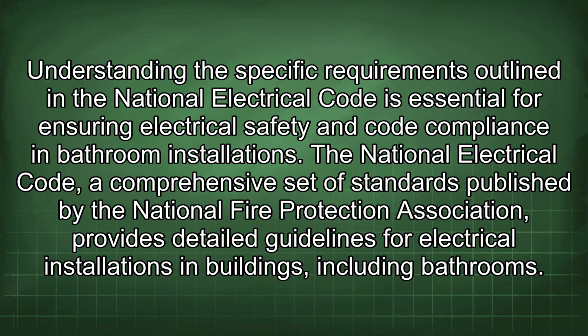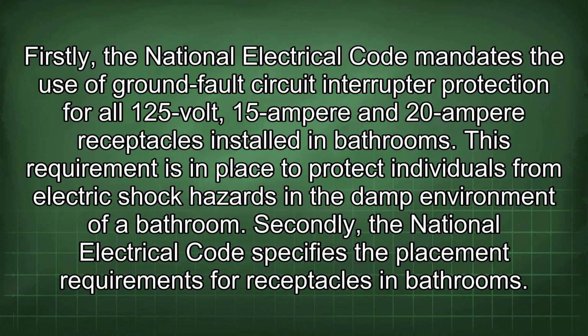Understanding the specific requirements outlined in the National Electrical Code is essential for ensuring electrical safety and code compliance in bathroom installations. The National Electrical Code, a comprehensive set of standards published by the National Fire Protection Association, provides detailed guidelines for electrical installations in buildings, including bathrooms. Firstly, the National Electrical Code mandates the use of ground fault circuit interrupter protection for all 125 volt, 15 ampere and 20 ampere receptacles installed in bathrooms. This requirement is in place to protect individuals from electric shock hazards in the damp environment of a bathroom.